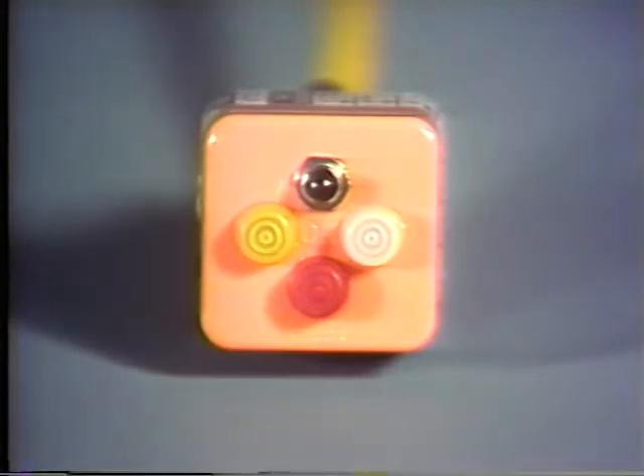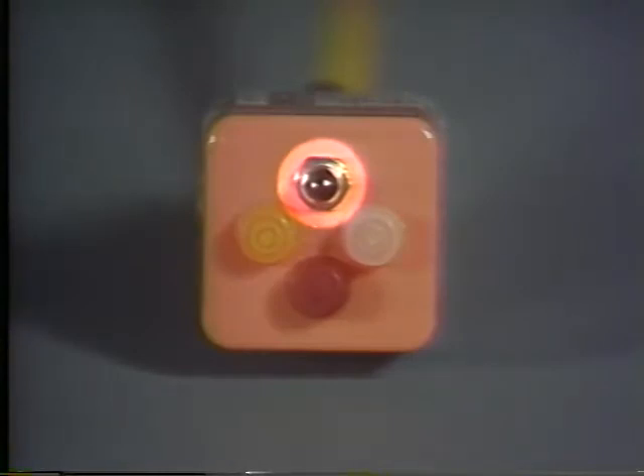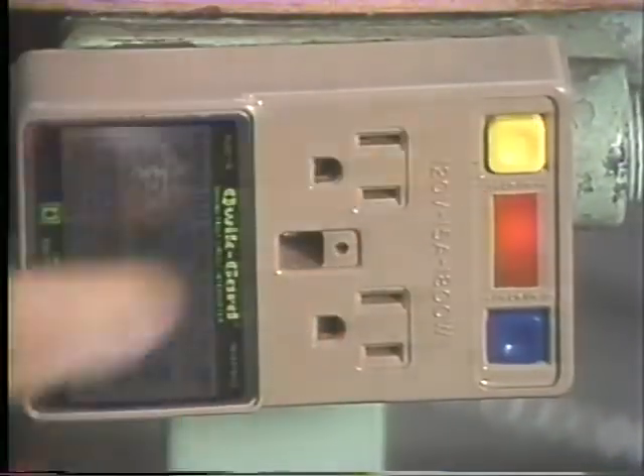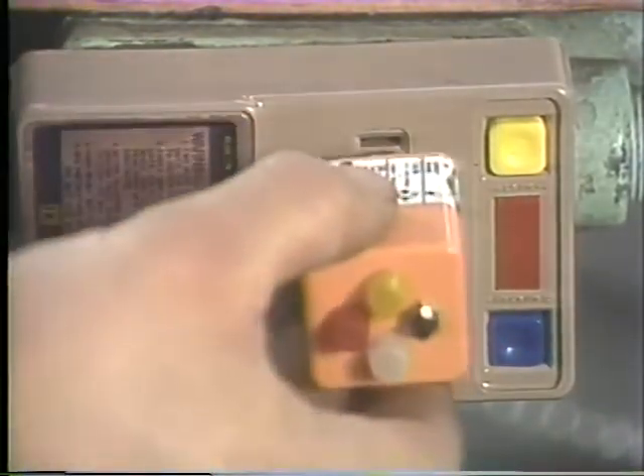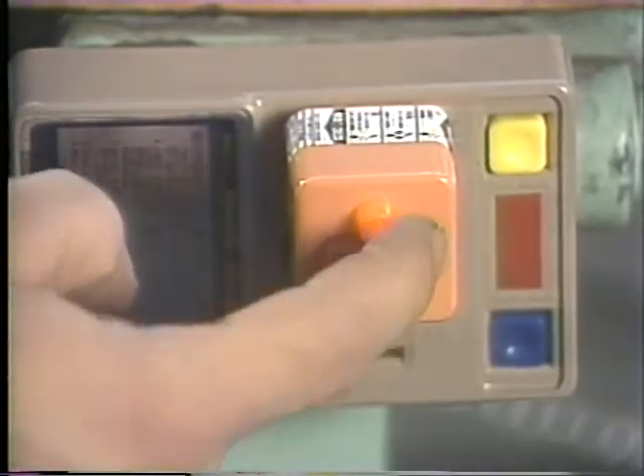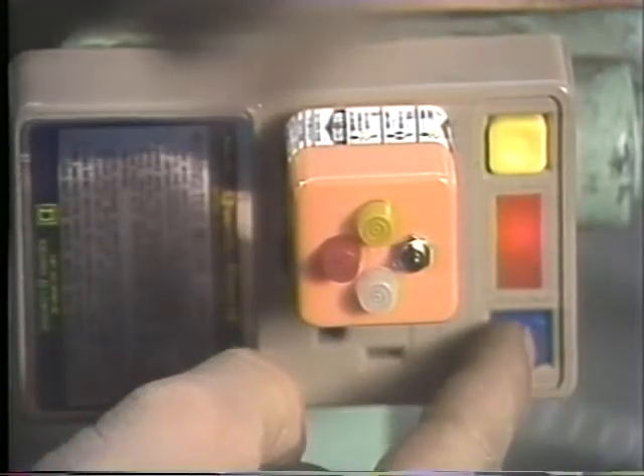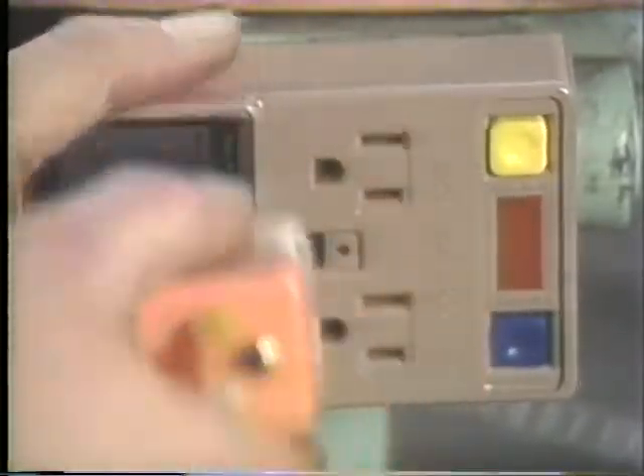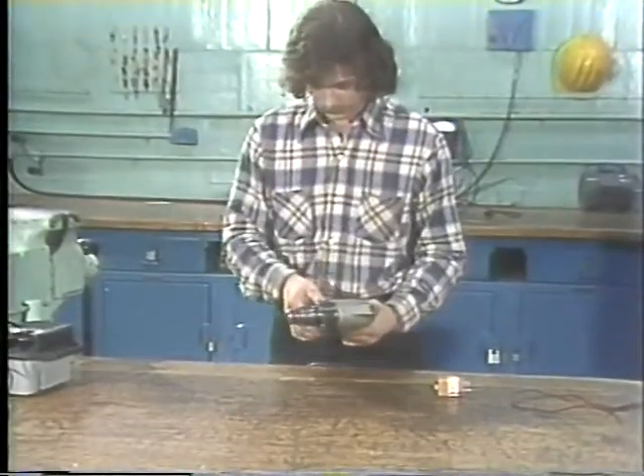A receptacle tester like this one tells you if a socket is properly grounded and whether it's wired with the correct polarity. If a socket's wired and grounded correctly, these two lights come on. As an added feature, this one also has a button for testing ground fault interrupters. So before testing the drill motor, he plugs in the GFI, tests it, and resets it. The receptacle tester indicates that the receptacle's properly wired and grounded, but he tests the GFI one more time just to be sure. Now he can go ahead and plug in the tool and test the action of the drill motor. Any fault to ground that went undetected before would trip the GFI almost as soon as he pulled the trigger.